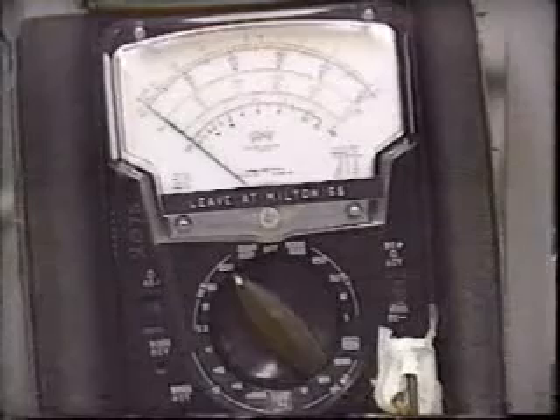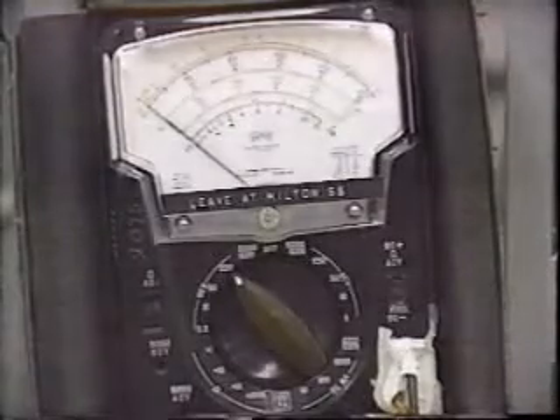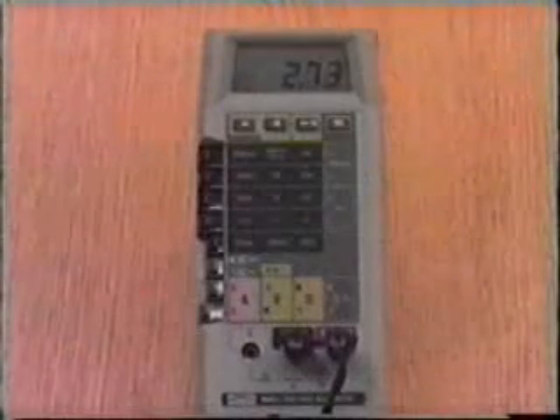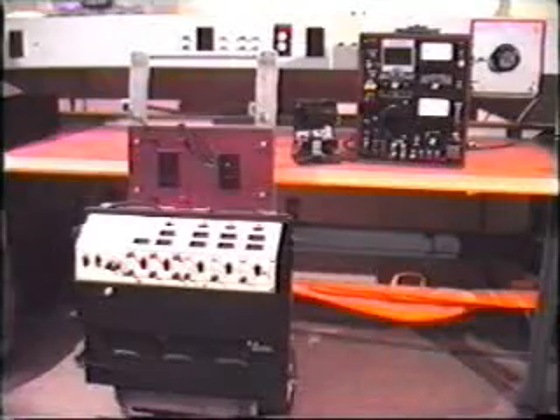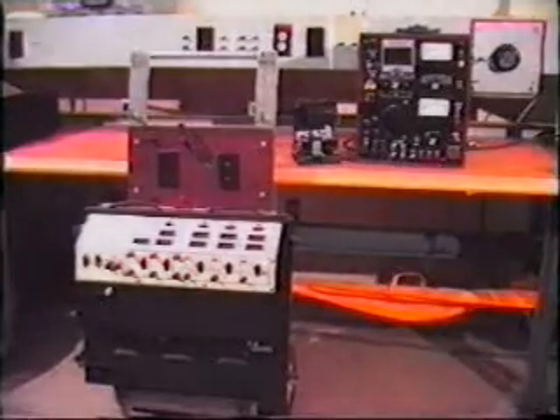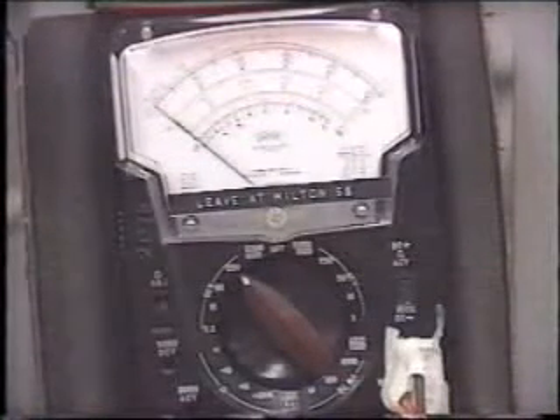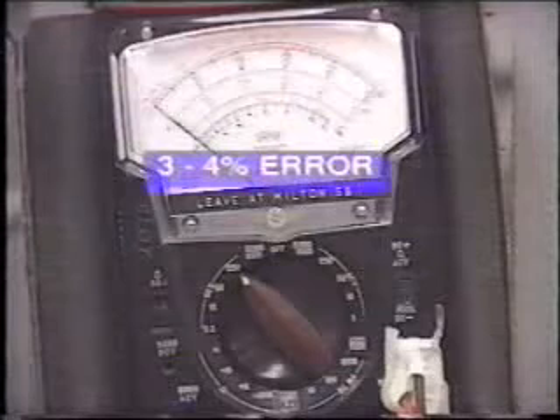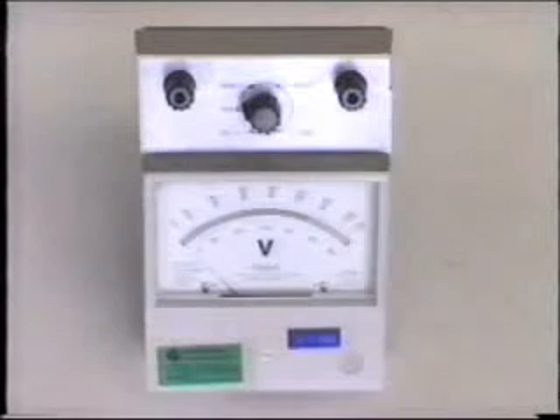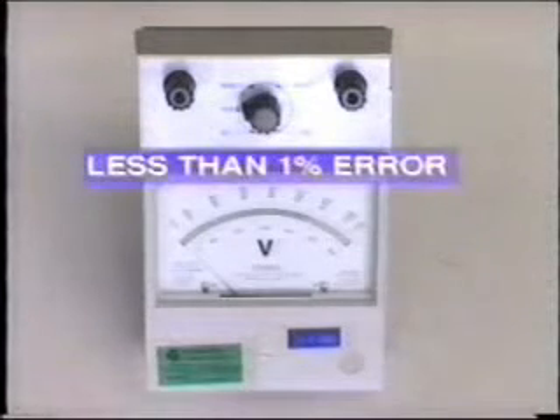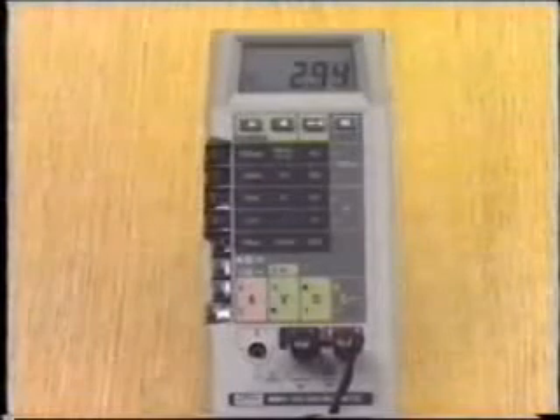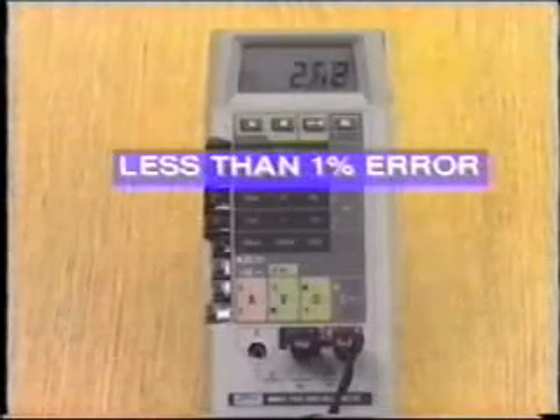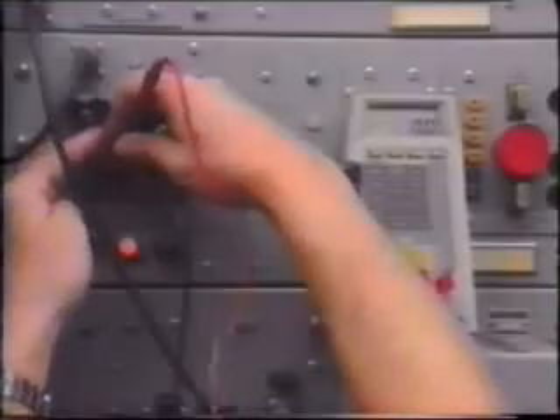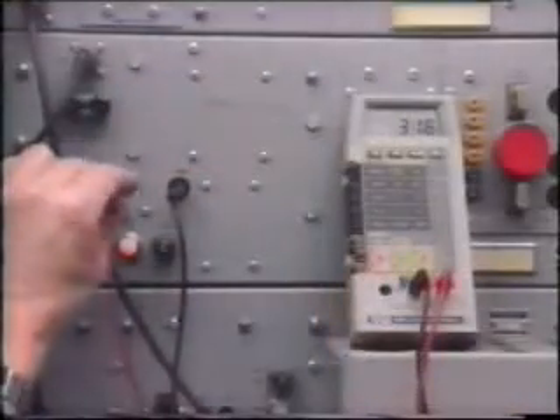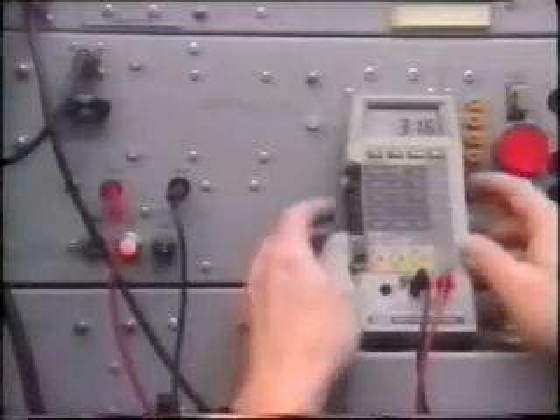These measurements may be taken by analog-type electromagnetic meters or, in recent years, digital instruments. One of our biggest concerns has to be the accuracy of the instrument. For example, this typical analog volt-ohm meter is liable to an error as high as 3 or even 4%. However, with this analog meter, the error is less than 1%. With digital meters, the accuracy is usually within 1%, except on the very inexpensive models. Digital instruments provide better resolution. The term resolution refers to the smallest reading increment that the user can observe.